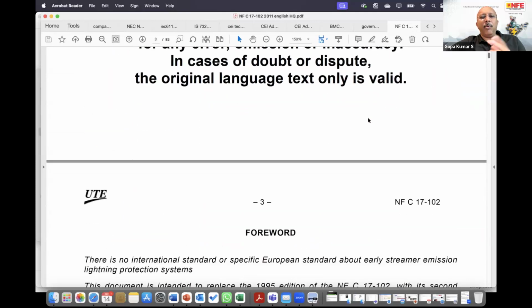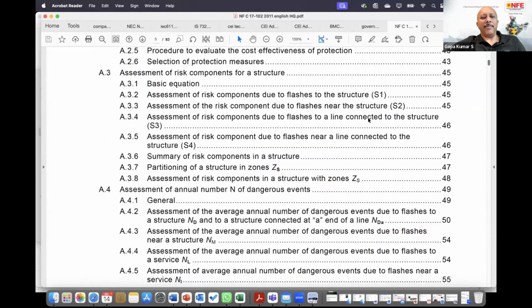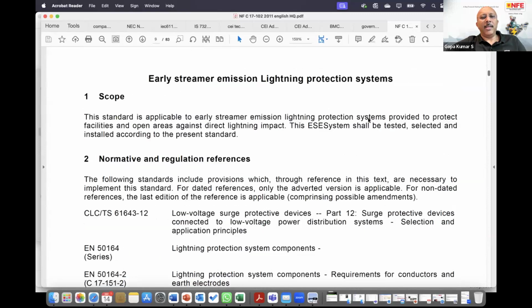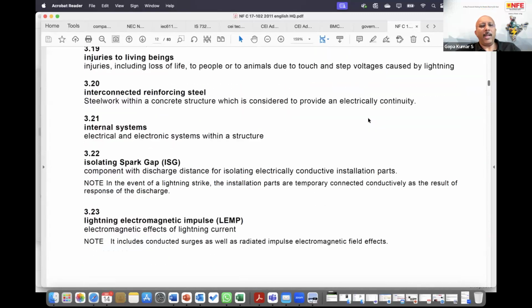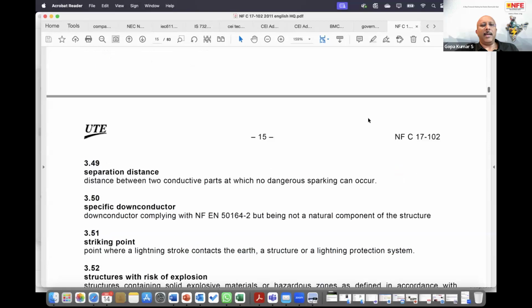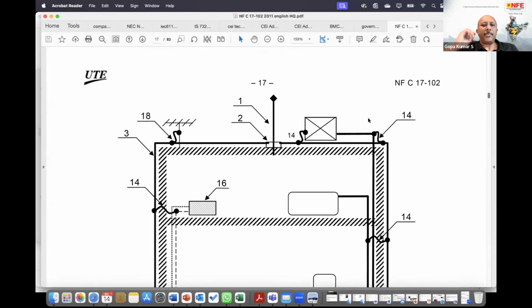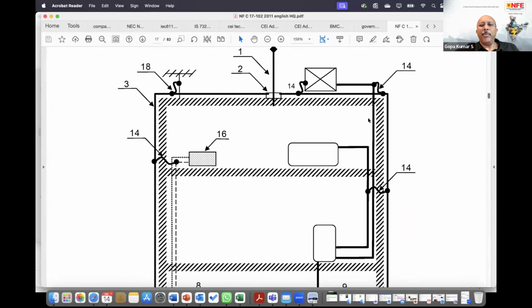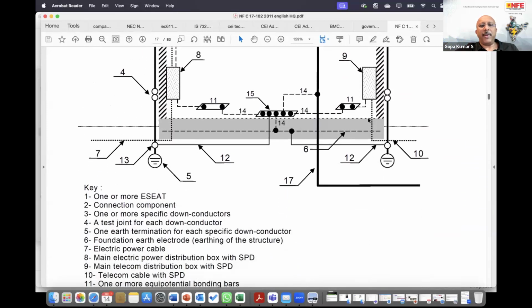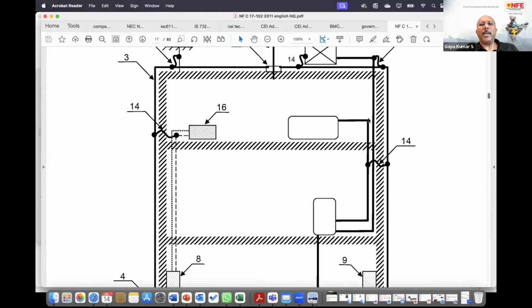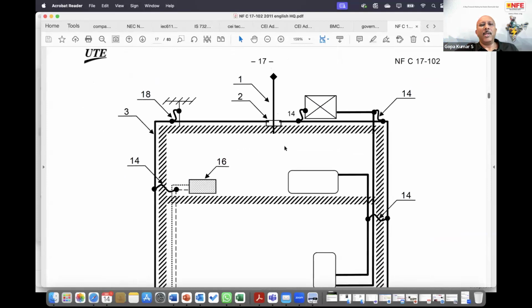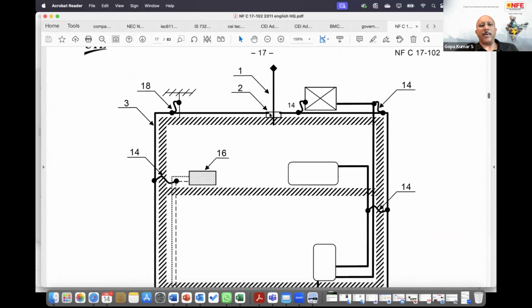or by standard. Now, where is this ESE used in such a condition? You can download the standard, go to figure number 1, and also read the entire parts of the standard. Figure 1 explains how this item is to be installed in a building. It consists of a perfect equipotential bonded building, so many bondings, so many down conductors, and finally an ESE rod. So in France, in buildings where lightning protection is mandatory by law, they put LPS as per 62305. Over and above, they put an ESE rod. That means additionally, you put an ESE rod.